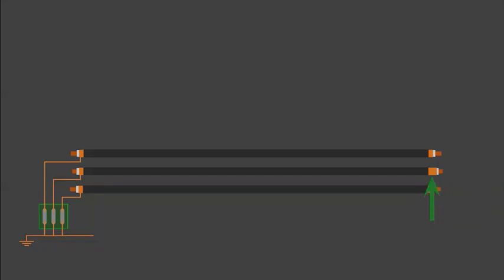That voltage is induced voltage due to the current in the conductor. And that voltage will be proportional to the length of the cable sheath. If the cable is very small in length, then the voltage that appears at the open end of the sheath will not be very big. But if this cable is long in length, that voltage may be a significant voltage. During faulty conditions, this voltage may appear much above the touch and step voltages, or it may deteriorate or damage the XLPE insulation of the cable. So there should be some arrangement so that that voltage hike can be avoided.